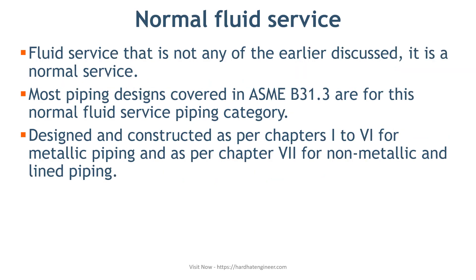The last service is normal fluid service. As the name suggests, if the fluid service for a pipeline is not any of the earlier discussed categories, it is a normal service. You go through the categories such as high pressure, elevated temperature, high purity, Category D and M — and then whatever is left is called normal service. Therefore, most piping design covered in ASME B31.3 is for the normal fluid service category. It is designed and constructed as per chapter 1 to chapter 6 for metallic piping and as per chapter 7 for non-metallic and lined piping.